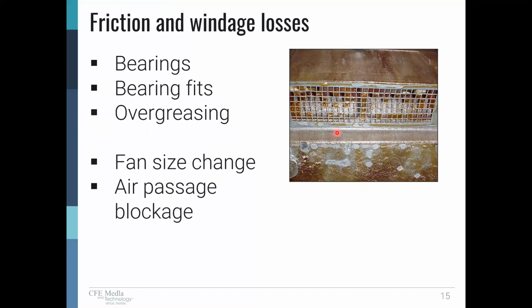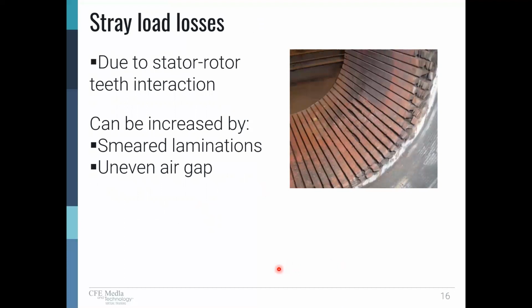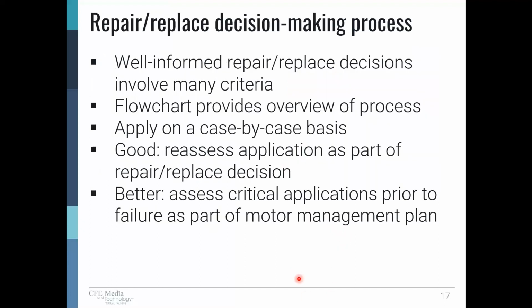Blocked air passages, here's just an example of a motor where some of the varnish from a winding process got on the screen and started blocking some of those vent holes. So that would be a restriction in airflow. So we want to make sure we've got full airflow going through the motor in the repair aspect. The stray load losses, things that can happen to the motor that affect the stray load loss. Smearing, in other words, if there was rubbing between the stator and the rotor, the rubbing on the stator core, that can increase the stray load losses. Same thing with the stray load losses being affected by the rub on the rotor. And uneven air gap. The rotor should be precisely centered in the middle of the stator. If it's off to one side, that's going to increase stray load losses. So that's our background to what it is about energy efficiency and what the losses are, what parts of the motor, and how they're affected by the losses.